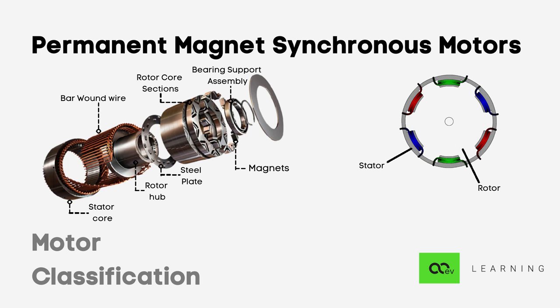The RMF has a direction which will be rotating. We know opposite poles attract and like poles repel. The stator's magnetic field and the rotor's field result in opposite poles attracting each other. The rotor is locked with the RMF and will start to rotate with the same speed as that of the RMF. One can observe that the rotor is spinning in synchronization with the RMF. Hence this motor is called a synchronous motor. There is no lag between the RMF and the rotor and thus there is no slip.